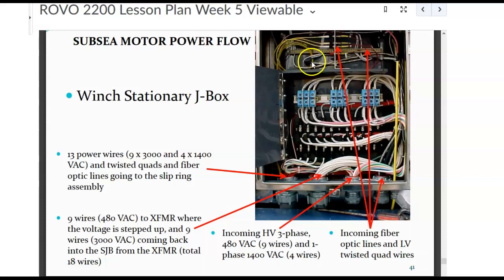Fiber optics got to be separate, okay, from your cabling. So what you got to have is nice bend radiuses. If it's tie wrapped, you got to be flush cut, so when you're sticking your hand in, you don't cut your hands on the jagged pieces. Screwed in tight, give it a tug test, right? Not to rip it out, but a good little tug test, 10-15 pounds tug force. It shouldn't be moving. Make sure you pick up your screwdriver afterwards, okay? And most important, lockout tagout procedure before you go into this box, so there's no live voltages in her, okay?